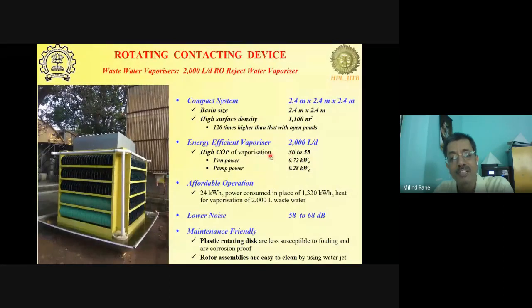Well, the COP is defined as the water vaporized into its latent heat of vaporization divided by the energy input to the fan and the pump. In this case, there was no heat being supplied here. The pump was pumping the water from the trough to the top, and then through the holes here in the pipe, the water will come out.